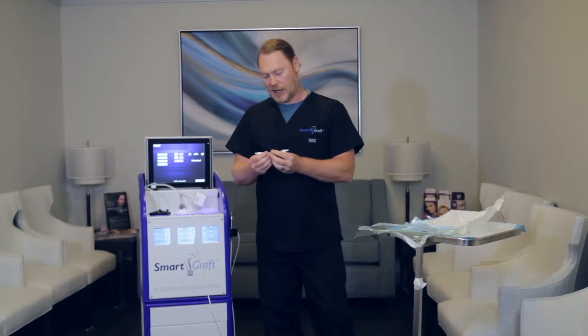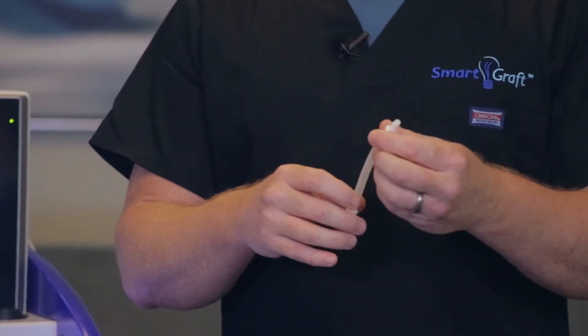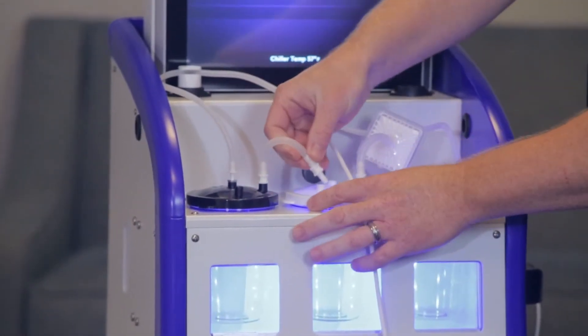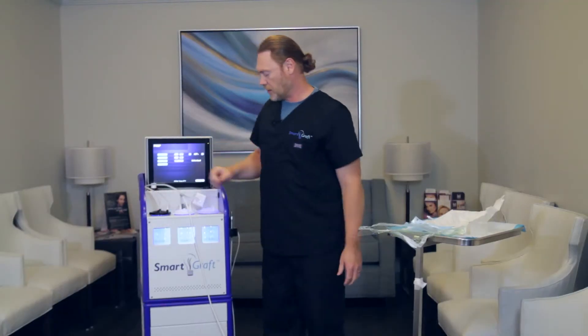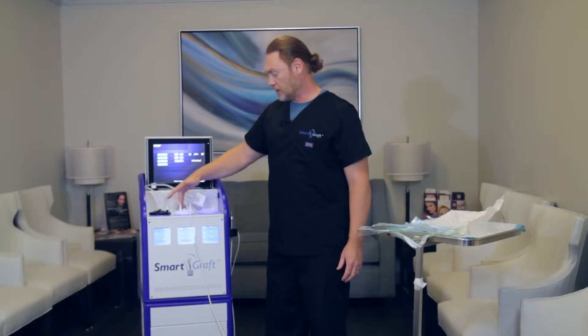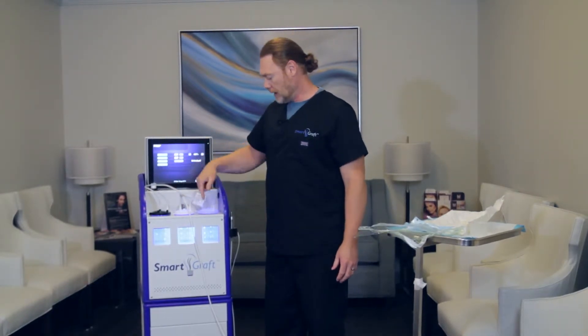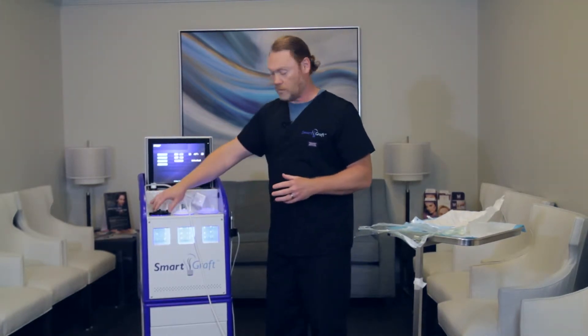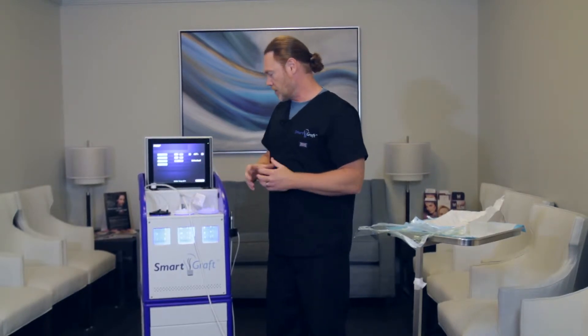The third tube actually has two different nozzles on it — both the same — and it's going to be going from the graft canister over to the overflow canister. Each one has a function here: this one is going to capture the grafts, this one is going to be the overflow saline from the misting, and this one is actually going to contain the saline itself to go over to the graft canisters to keep the grafts wet. That's the basic graft canister setup.